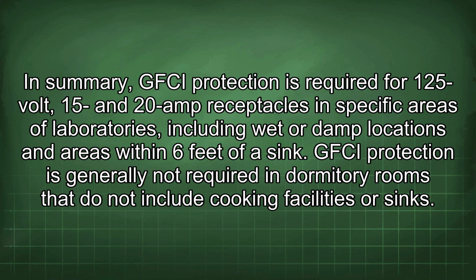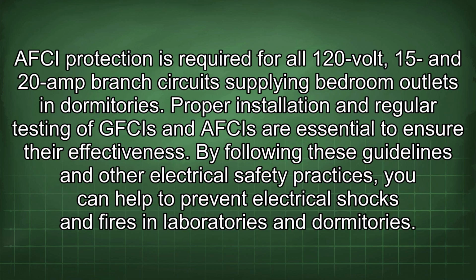In summary, GFCI protection is required for 125 volt, 15 and 20 amp receptacles in specific areas of laboratories, including wet or damp locations and areas within 6 feet of a sink. GFCI protection is generally not required in dormitory rooms that do not include cooking facilities or sinks. AFCI protection is required for all 120 volt, 15 and 20 amp branch circuits supplying bedroom outlets in dormitories. Proper installation and regular testing of GFCIs and AFCIs are essential to ensure their effectiveness. By following these guidelines and other electrical safety practices, you can help to prevent electrical shocks and fires in laboratories and dormitories.